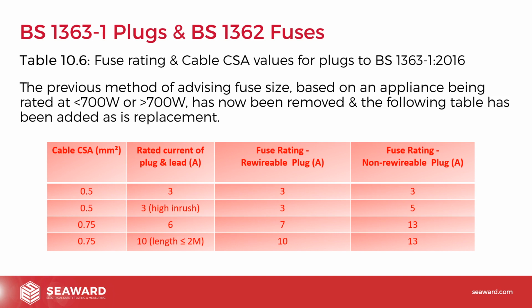So yeah, it was nice and easy before when we had the 700 watts. Is it less than? Is it greater than? And then we'd pick the ratings based off that. But obviously that didn't always align with what we were seeing in real life in the field. And hopefully now the tables that are in there give you the values that are likely to align with what the manufacturers selected when they've designed their equipment. But really what we would recommend is using the manufacturer's figures where they're known.